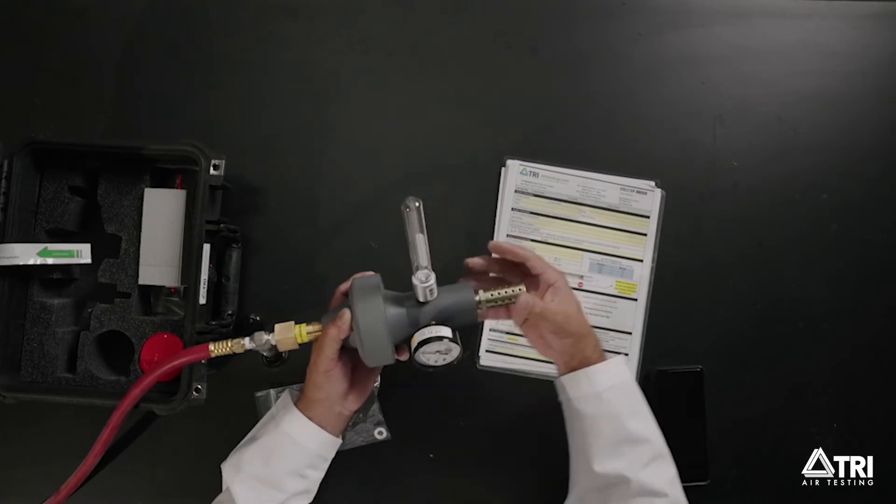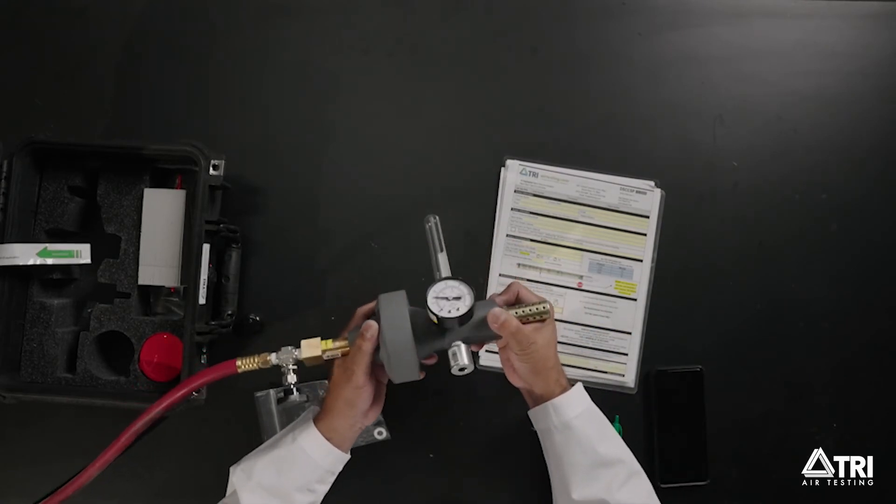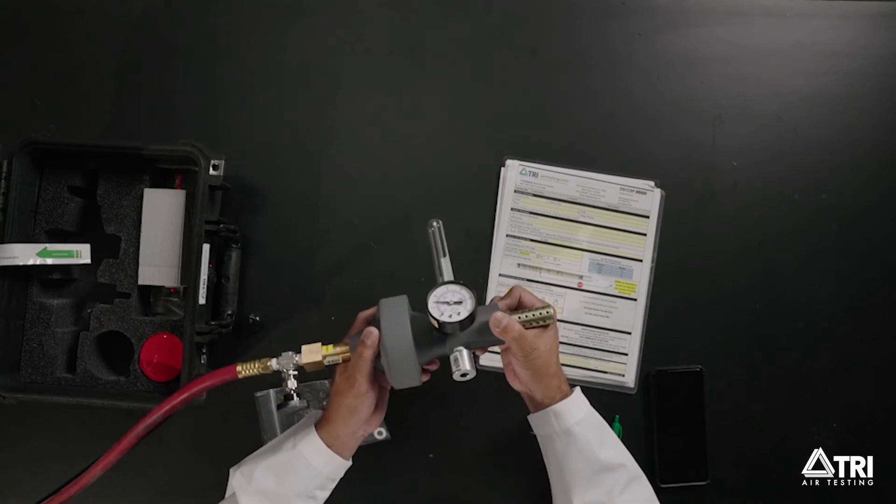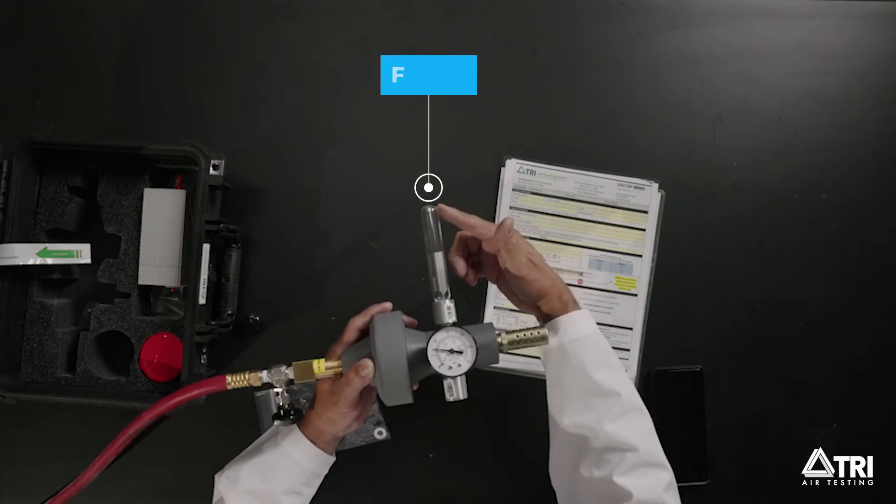Do not twist the bottle as the needles will be damaged. The gas sample bottle must run at least one minute. Be sure to check that the white plastic float inside the sample bottle has risen away from the needled fitting.